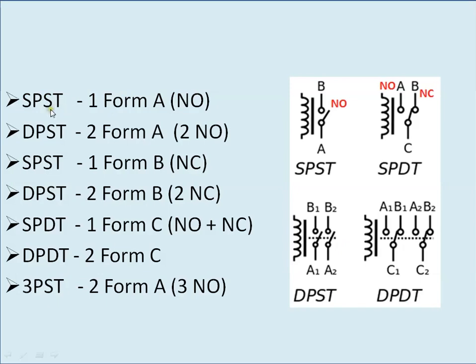These are the different names for the form ratings. For a relay requiring a single pole single throw, it can be defined as one Form A, which has one NO contact. If your application requires two NOs, you select two Form A contact rating, which is also known as double pole single throw — it has two poles and one throw, meaning only one position which is the NO position.